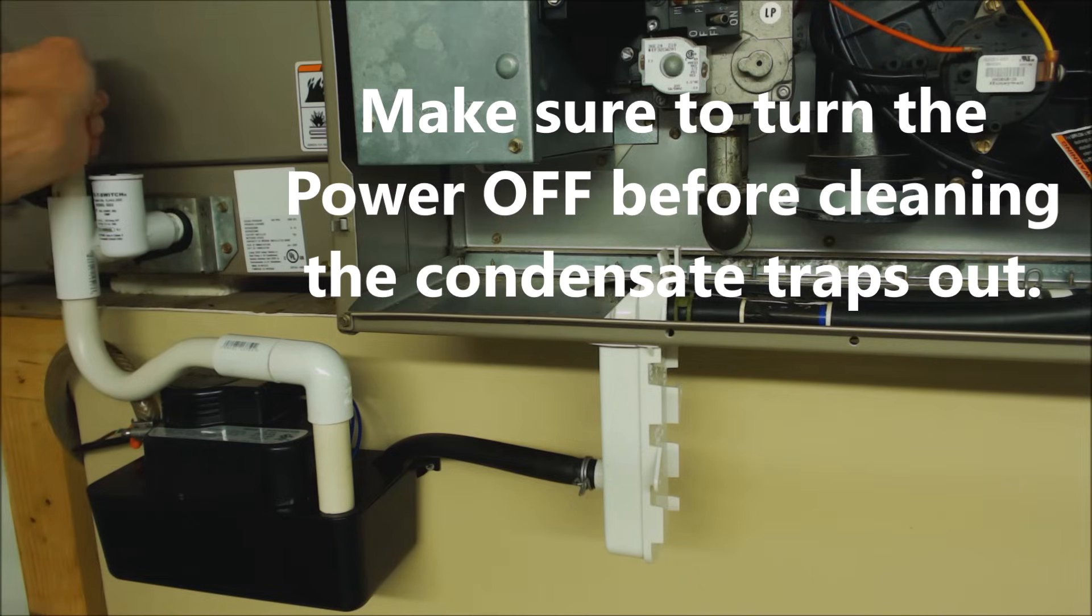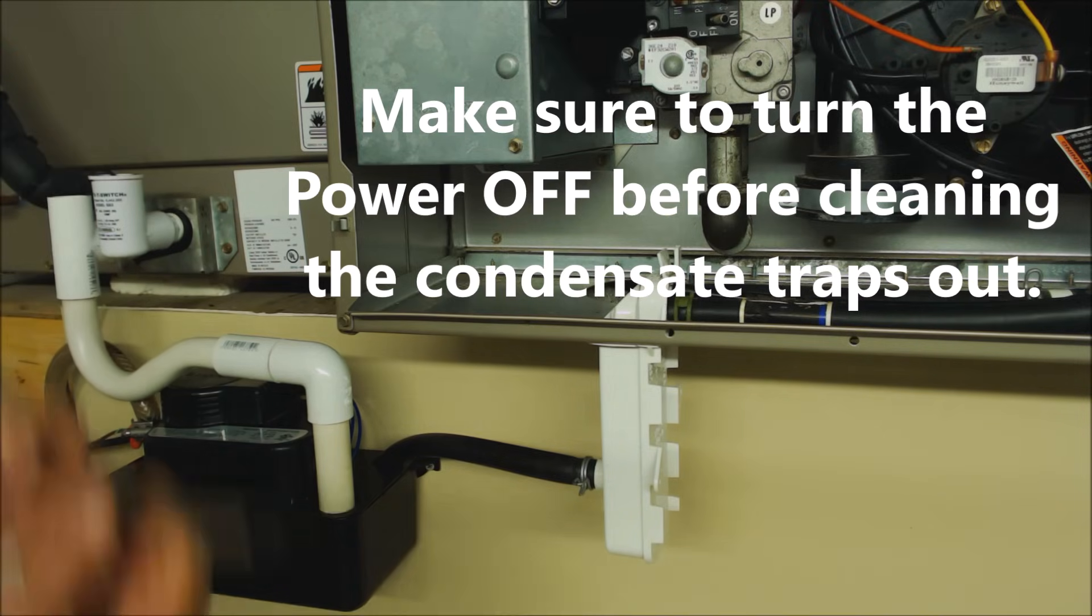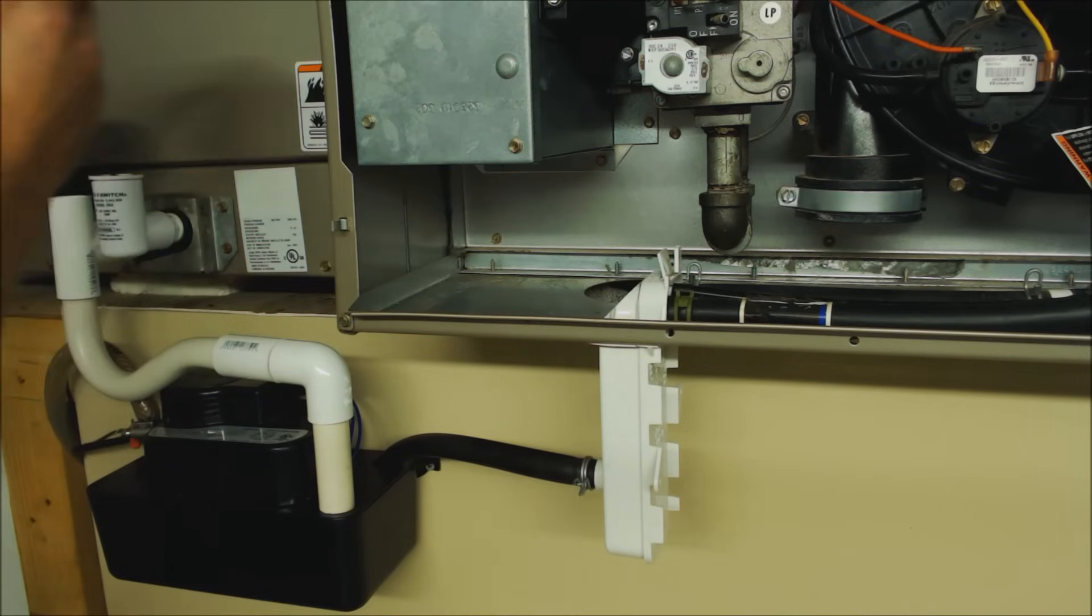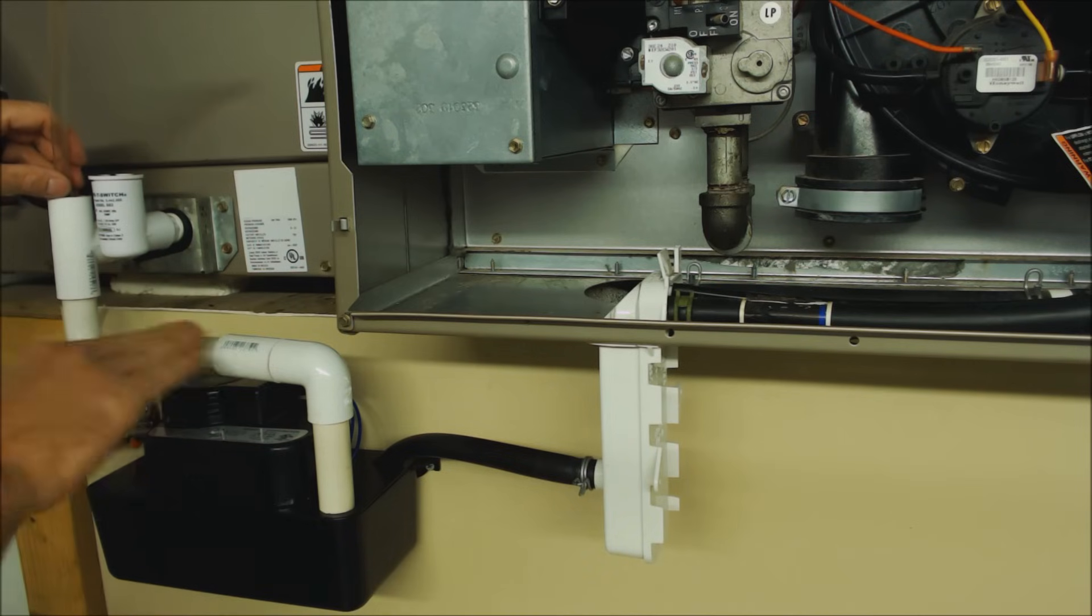So a simple technique is just to blow it out with a ten cent piece of clear vinyl tubing and then some electrical tape. You just stick that right down in there and then you go ahead and blow and that pushes it forward. The issue is it's still in there but at least you got that unclogged and the system will operate.